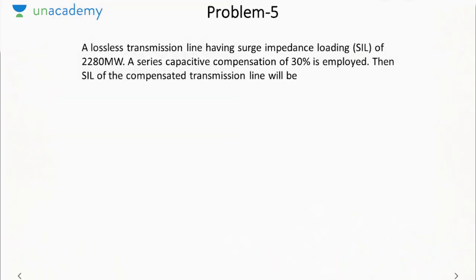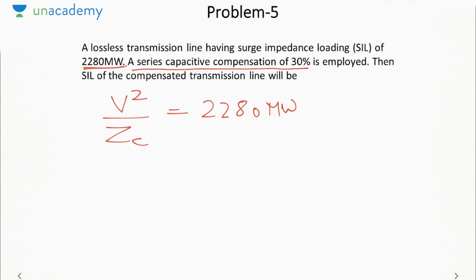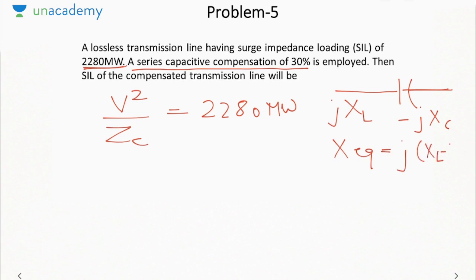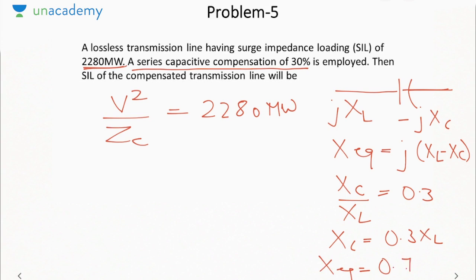In our next problem, it is saying a lossless transmission line having a SIL of 2280. So V square by ZC is given as 2280 megawatt. Okay. A series capacitive compensation of 30%. What does series capacitive compensation mean? In a transmission line, we are connecting a series capacitor. If it has a reactance XL, it will have minus JXC. So X equivalent will be J of XL minus XC. 30% means XC by XL is 0.3. So XC will be 0.3 XL, or we can say X equivalent will be 0.7 XL.